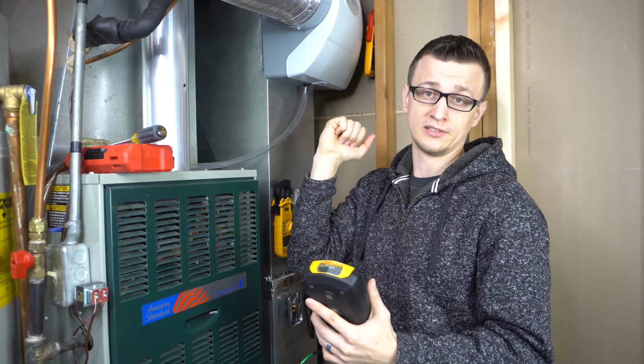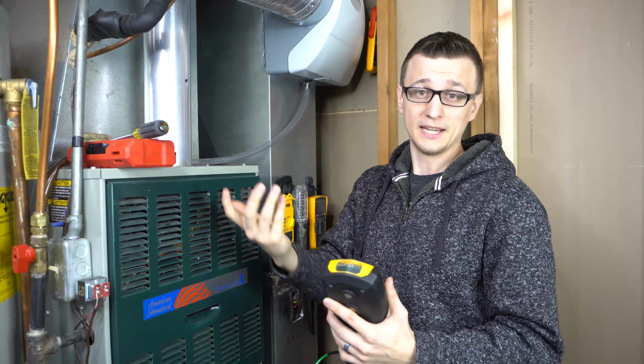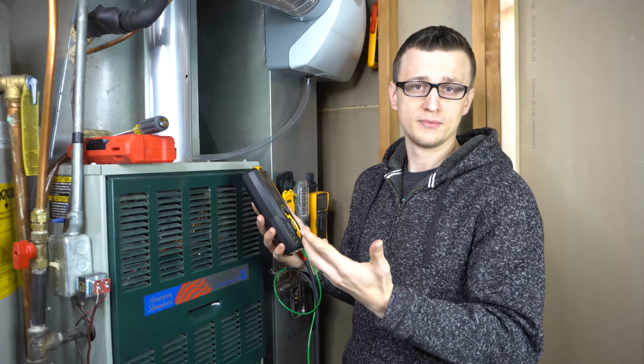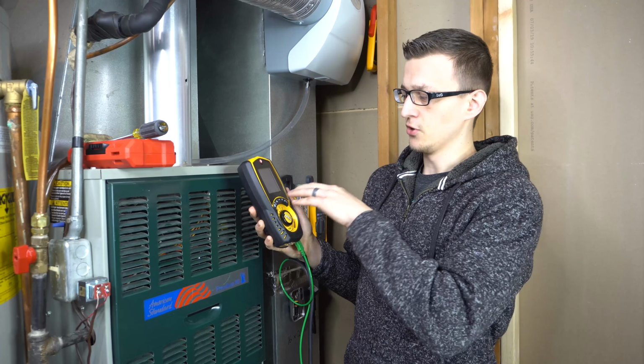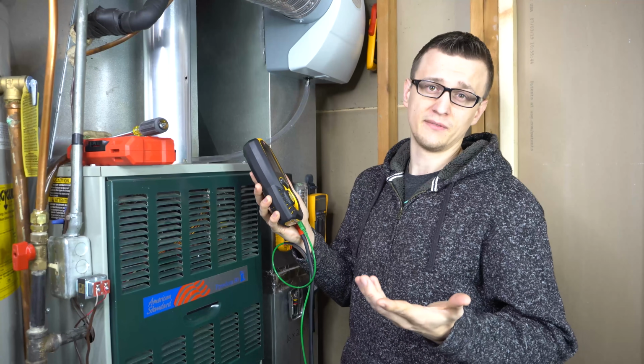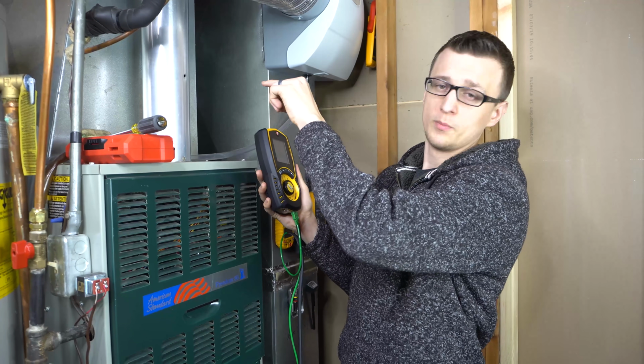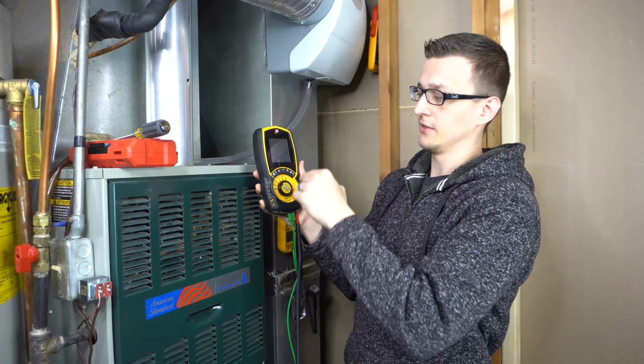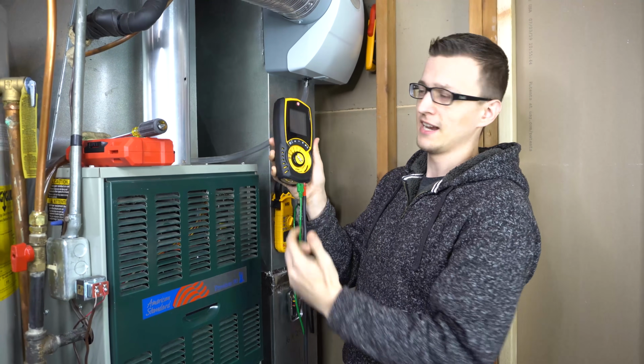out your probe immediately. If you leave it in there, that can peg your meter and pretty much destroy your carbon monoxide sensor, and then your analyzer will be out of commission until you get that fixed. So don't leave your probe in there if you see your carbon monoxide just skyrocketing. Don't try to set any records.